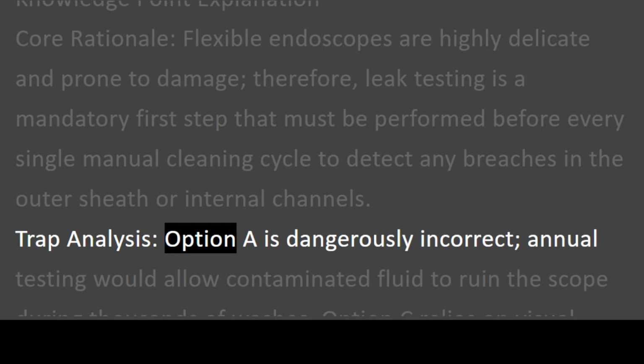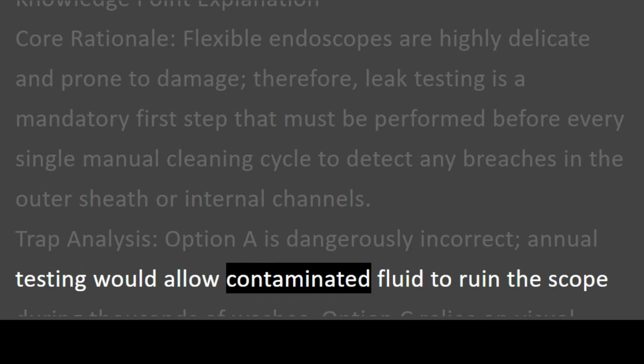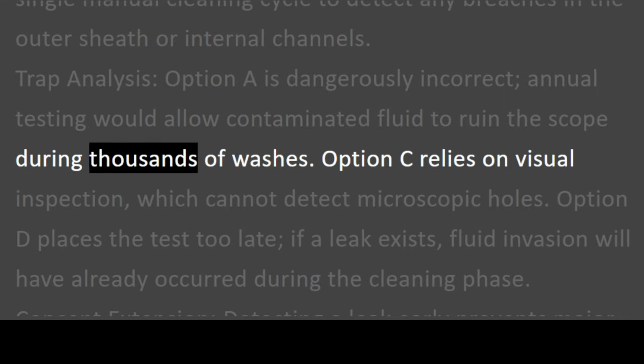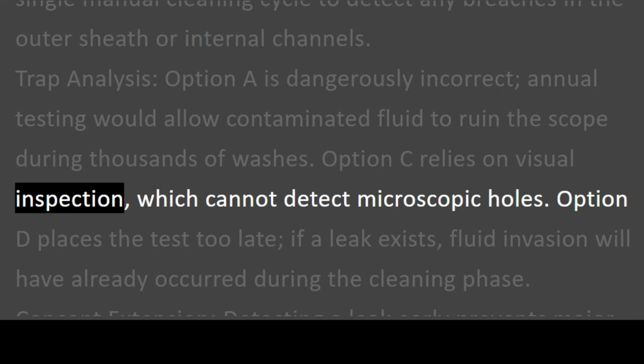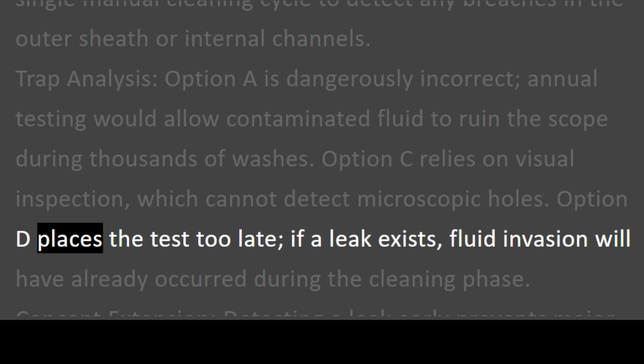Trap analysis. Option A is dangerously incorrect. Annual testing would allow contaminated fluid to ruin the scope during thousands of washes. Option C relies on visual inspection, which cannot detect microscopic holes. Option D places the test too late. If a leak exists, fluid invasion will have already occurred during the cleaning phase.